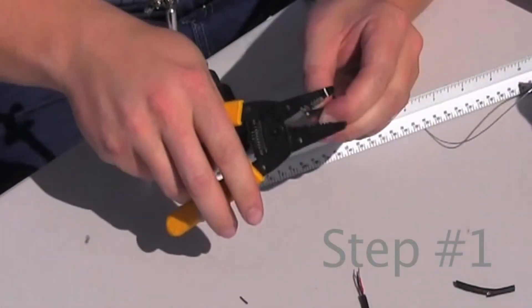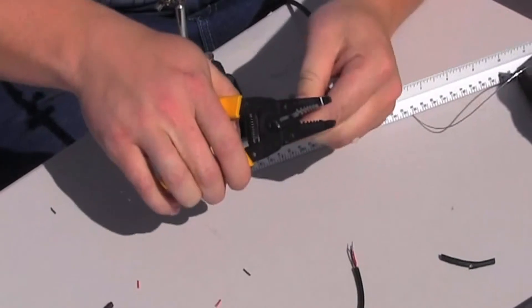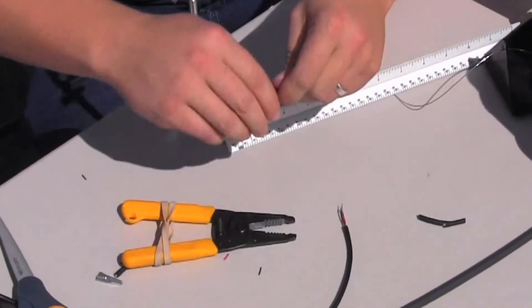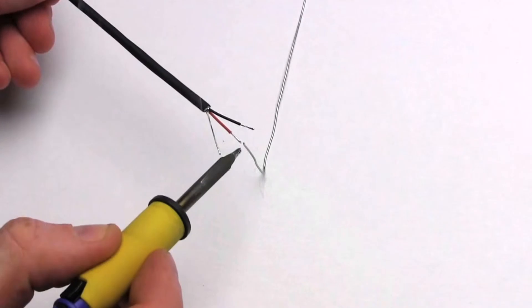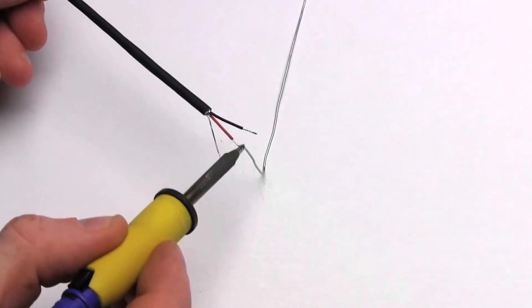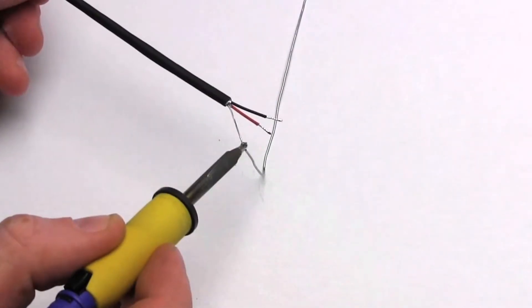Step one: strip the outer cable insulation 5 eighths of an inch while stripping and tinning the individual wires 1 quarter of an inch. Note that tinning the individual lead wires helps to eliminate cold solder joints by cleaning the individual strands and allowing solder to flow more freely.